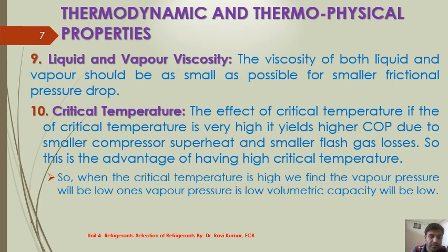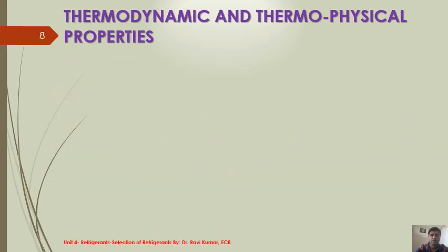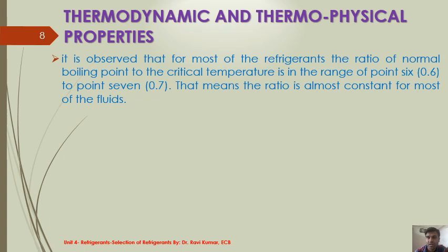When the critical temperature is high, the vapor pressure will be low and the volumetric capacity will be low. It is observed that for most refrigerants, the ratio of normal boiling point to critical temperature is in the range of 0.6 to 0.7, meaning this ratio is almost constant for most fluids. So high critical temperature gives higher COP but lower volumetric capacity — again, a trade-off between high COP and high volumetric capacity.